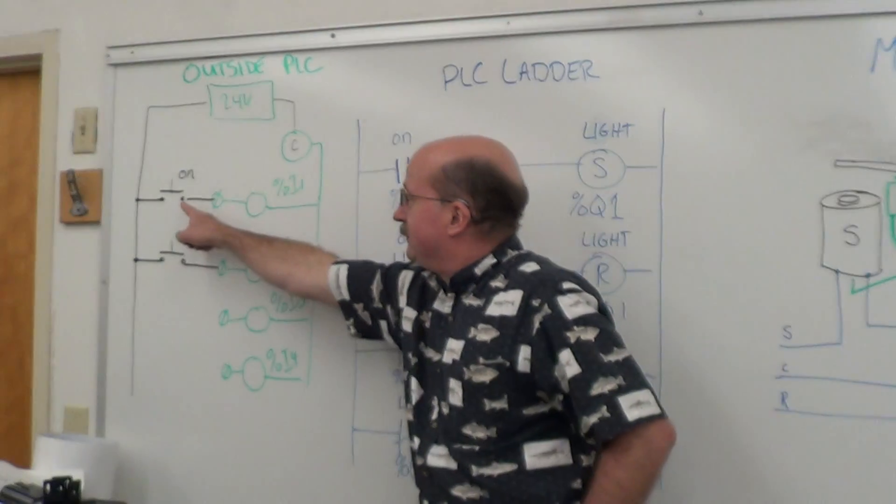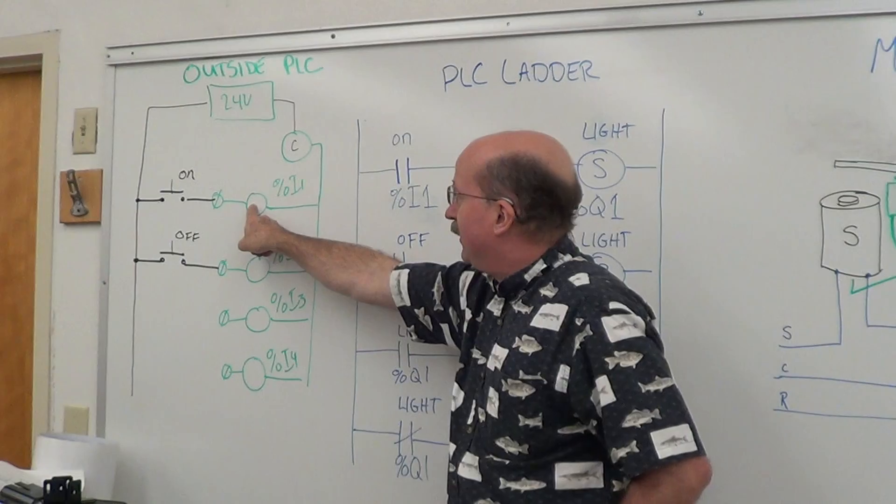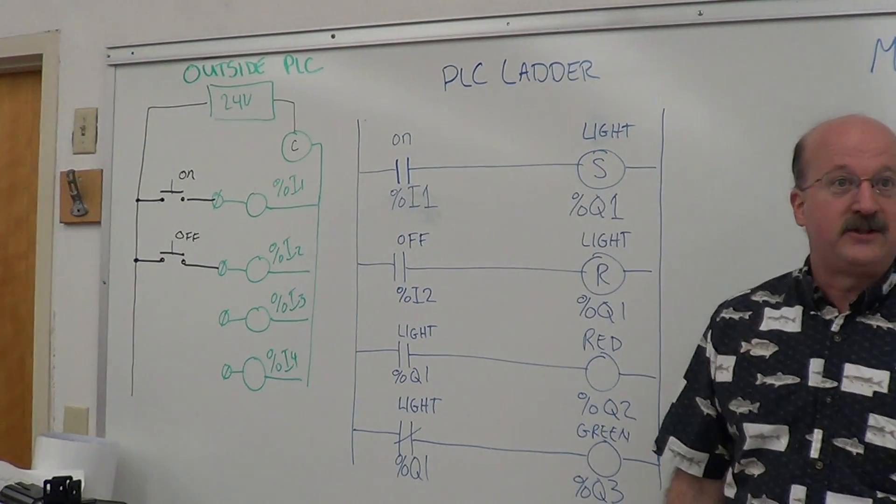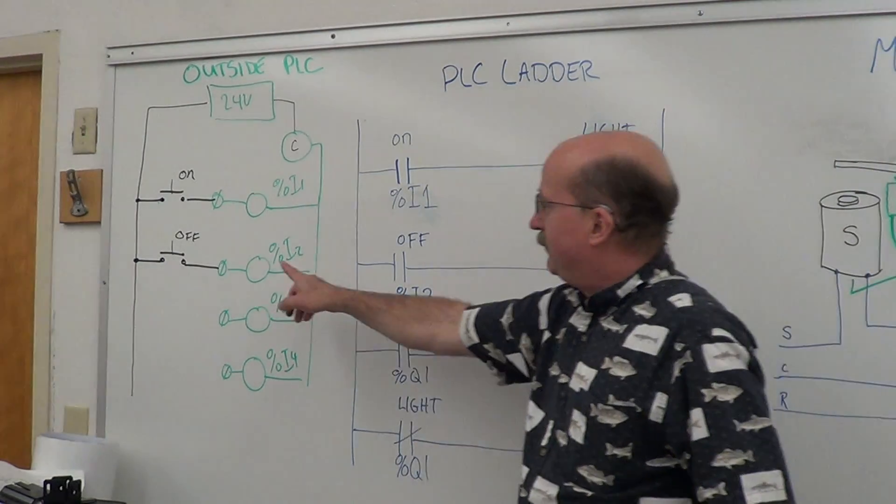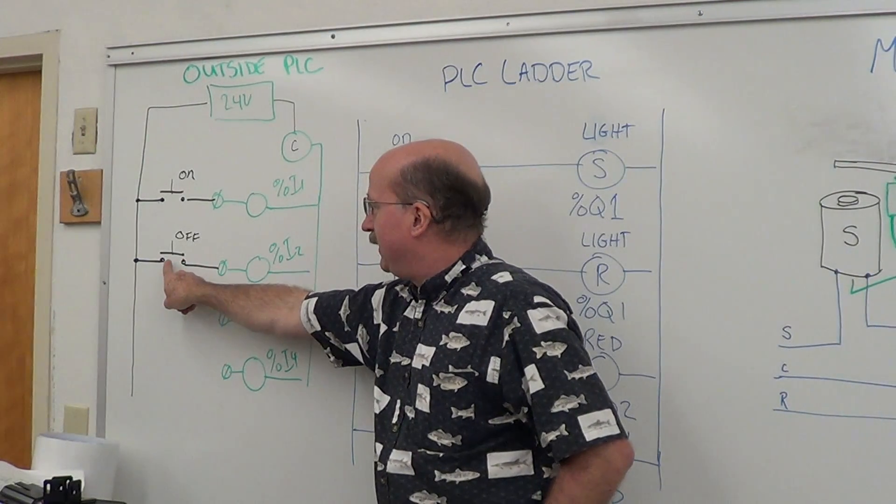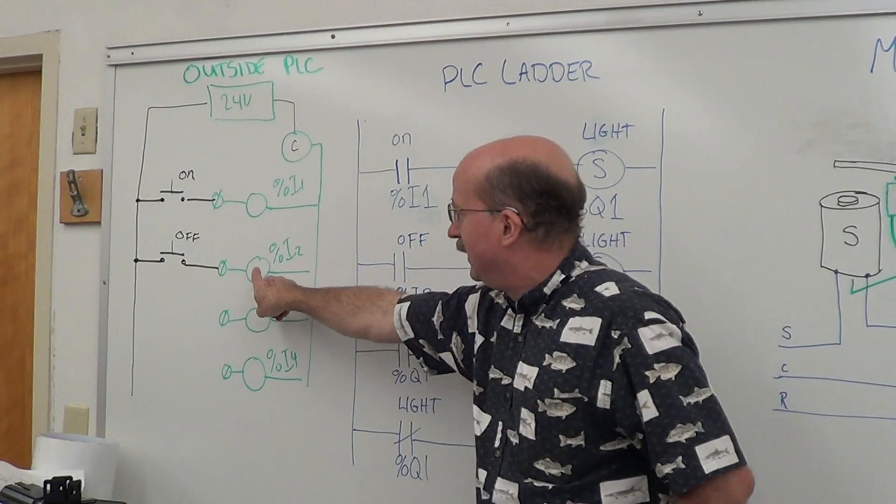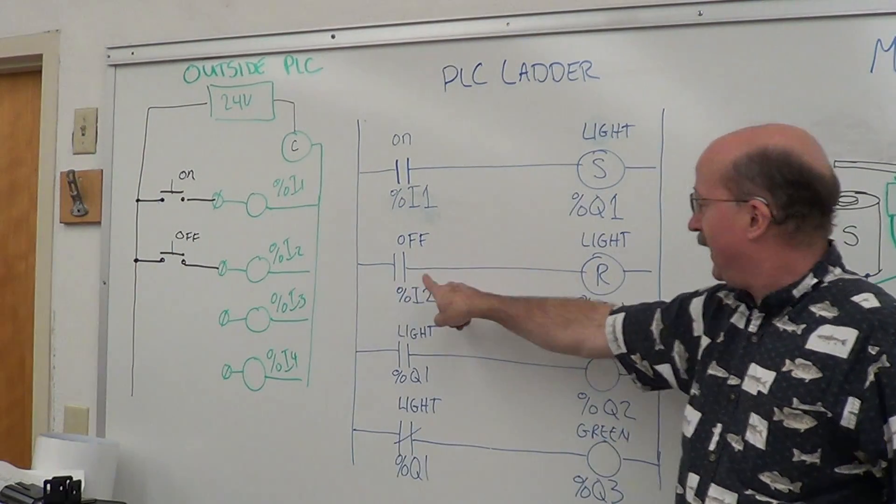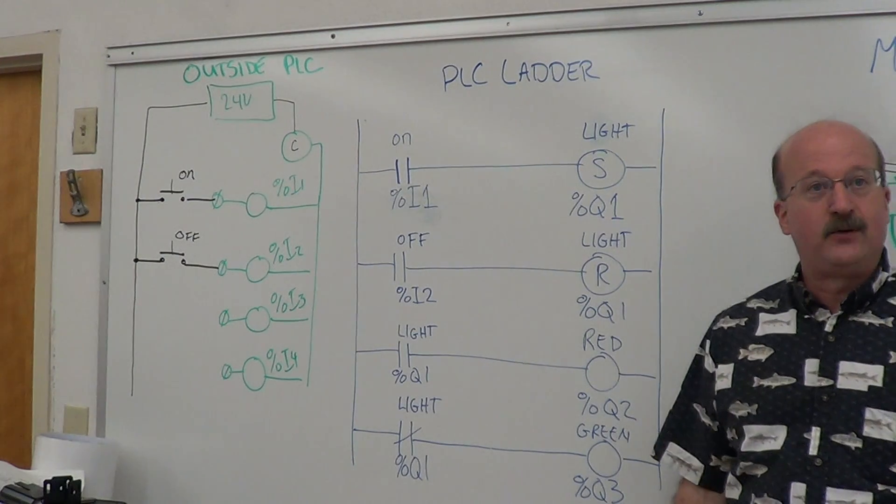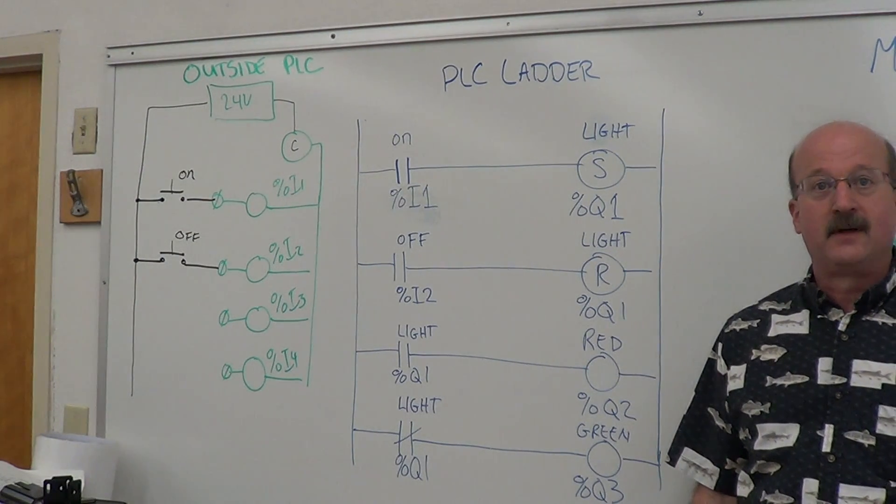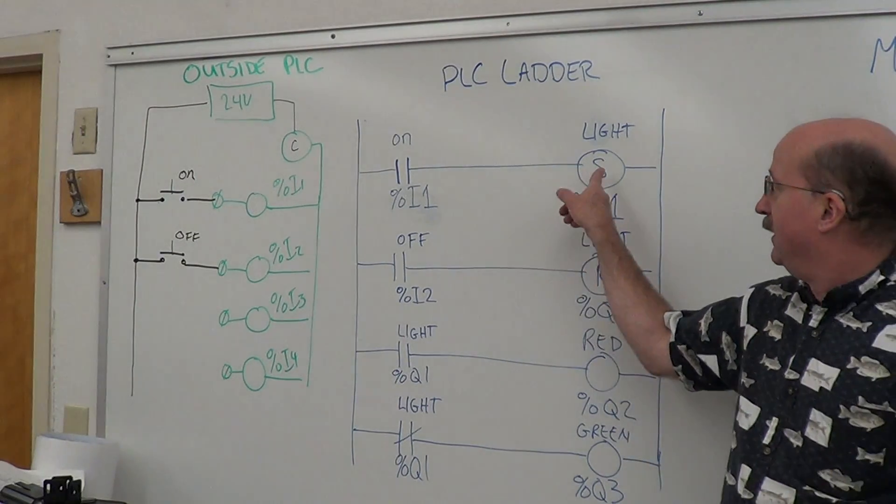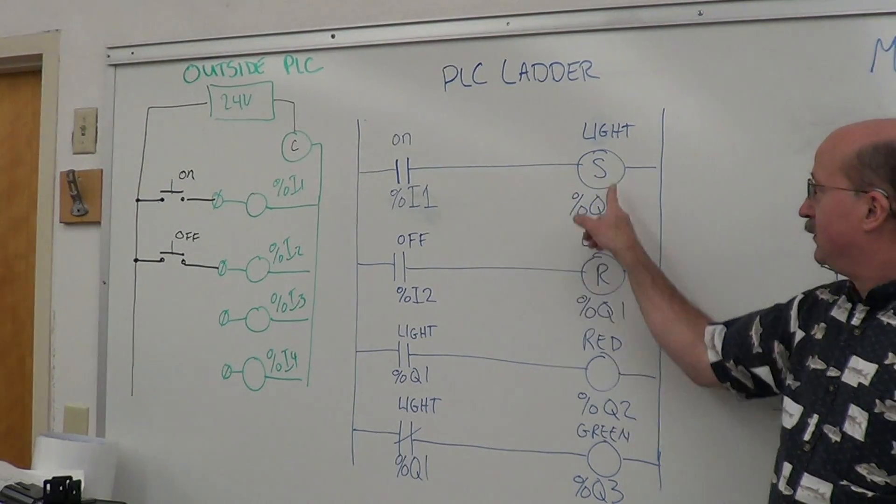If I push the on switch, the on push button, it'll energize this coil, close those contacts, energize your set relay. Same thing on this: if I push the off button, it'll close those contacts, energize your input coil, close these contacts, and put it into a reset mode. Very similar. All you need is a momentary input on here to turn it on or off.